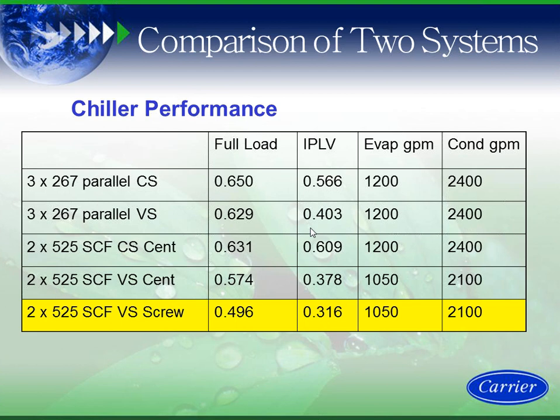On the condenser side, the reason why I can't reduce my condenser water GPM is because my lift, when I sized that original 267 ton machine, is based on 2,400 GPM of flow. When I reduce the flow, I increase my lift, which may cause the chiller to go to surge, which the variable speed screw can't do.